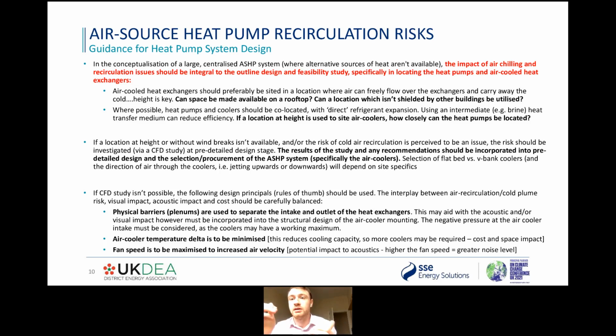Obviously, the higher up these are, the higher the rate of airflow over the air-cooled heat exchangers, dragging that cold air away. So can you put it on a rooftop? And if you can't, can you put it somewhere that isn't shielded by other buildings in the area? Because that has a quite drastic effect on air recirculation.